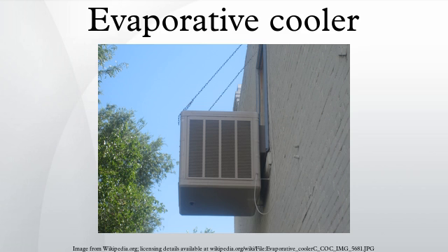At 32 degrees and 50% relative humidity, air may be cooled to about 24 degrees. The dew point for these conditions is 20 degrees. At 40 degrees and 15% relative humidity, air may be cooled to nearly 21 degrees. The dew point for these conditions is 8 degrees. Cooling examples extracted from the June 25, 2000 University of Idaho publication, HomeWise.